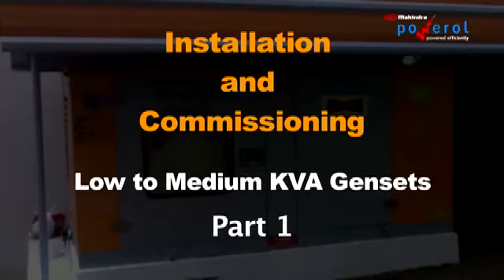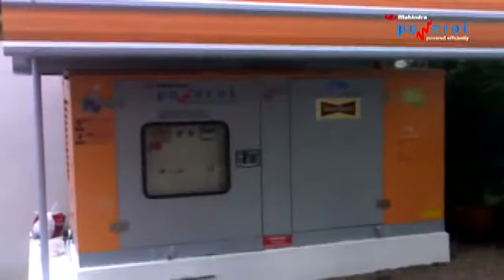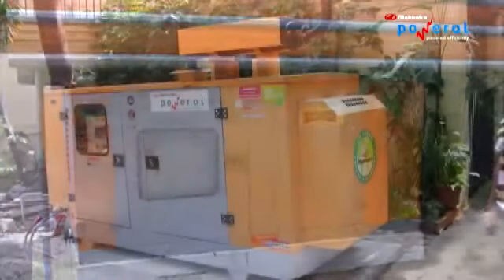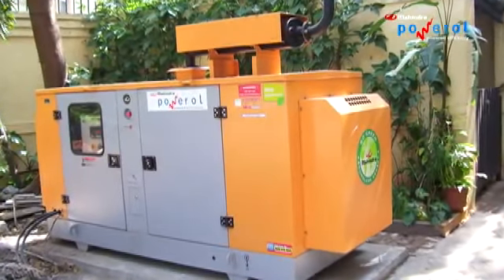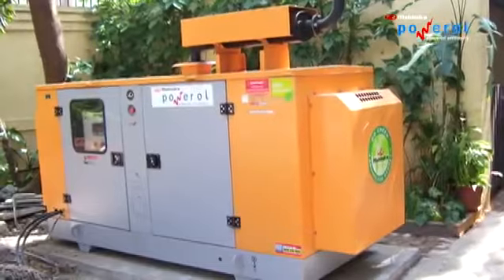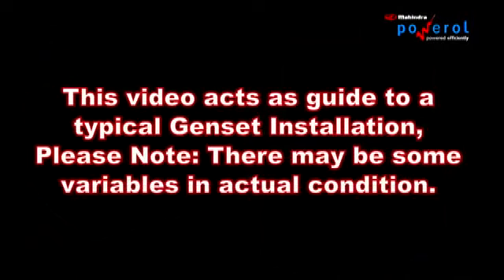Installation and commissioning. Low to medium kVA canopy gensets. Proper installation and commissioning of a genset is very important to achieve better uptime and safety. This video acts as a guide to a typical genset installation. Please note there may be some variables in actual condition.